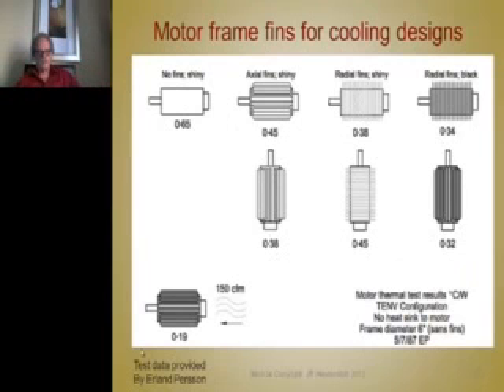Oh, here's a case where you've got a black motor with fins. This machine here, and they blew 150 cubic feet a minute across this thing through a fan mounted on the end. And the degree C is 0.19 degrees C per watt. Significant difference over this guy to that guy, or any of these. It's quite impressive.